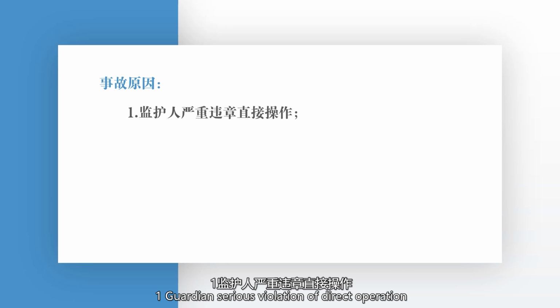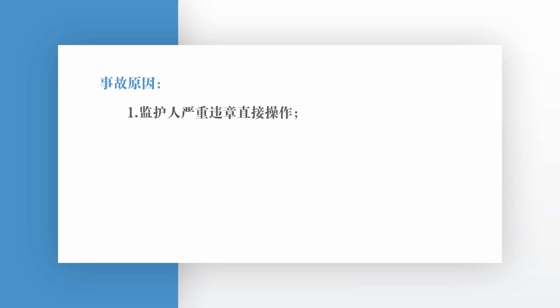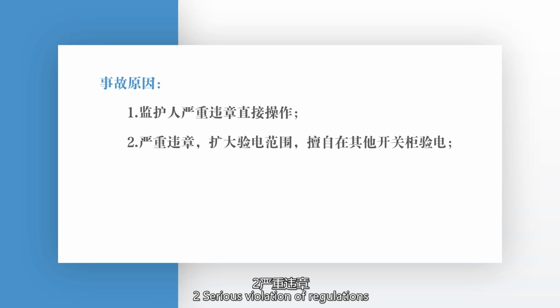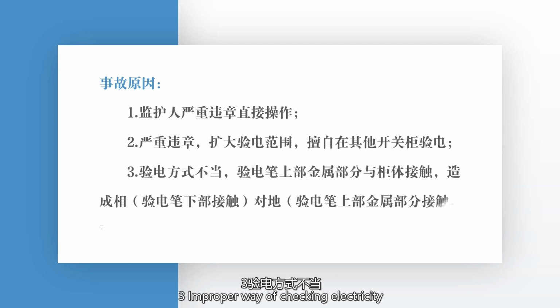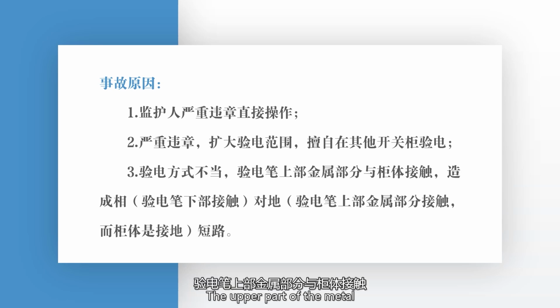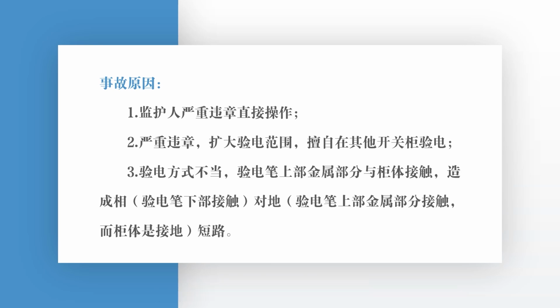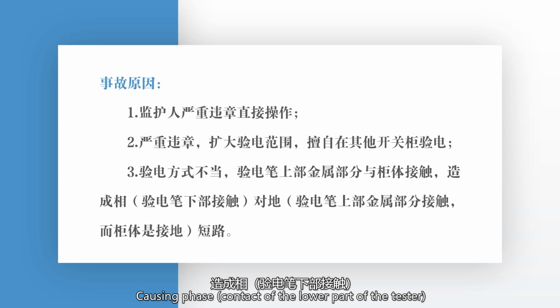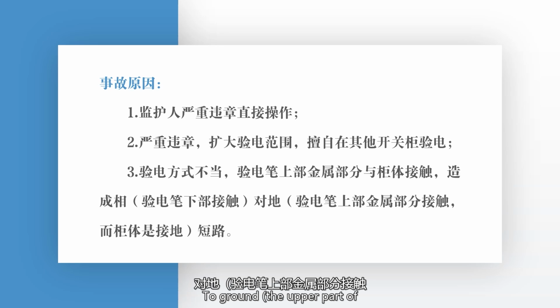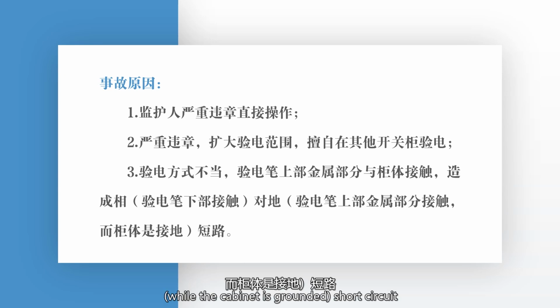Cause of the accident. 1. Guardian seriously violated regulations by directly operating. 2. Serious violation of regulation: expanding the scope of power testing, unauthorized power test in other switch gear. 3. Improper way of checking electricity. The upper part of the metal part of the electric tester pen and the cabinet contacted, causing phase contact of the lower part of the tester to ground. The upper part of the metal part of the tester contacts the cabinet, which is grounded, causing a short circuit.